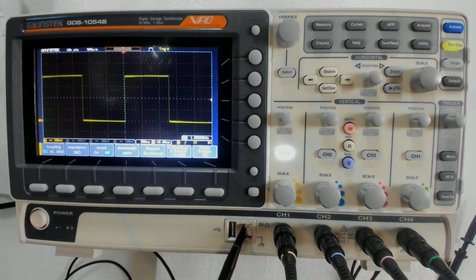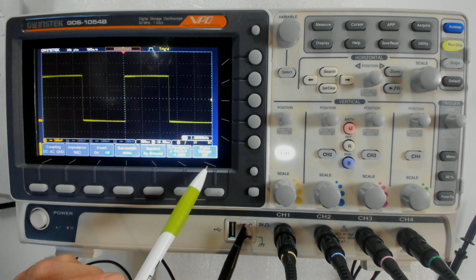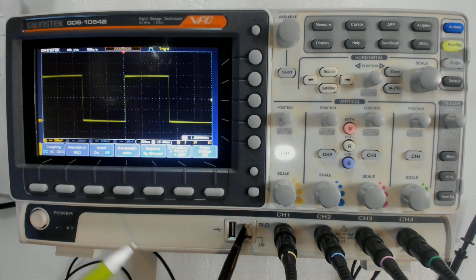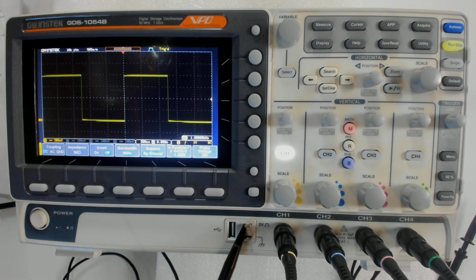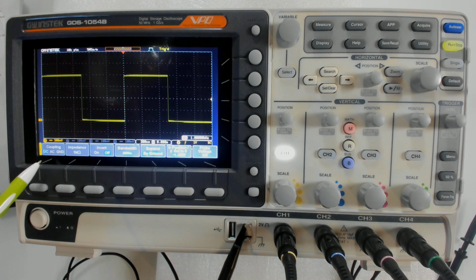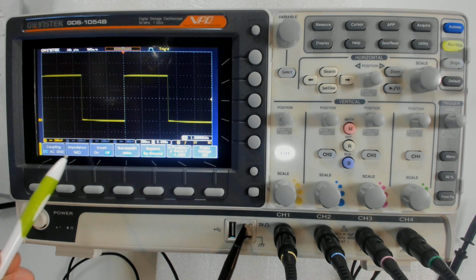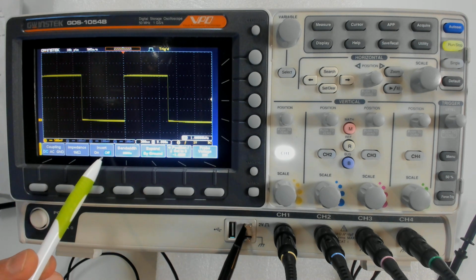Some of the highlights you can see are, I mean, you can see I took averaging off, right? I got sort of that thicker line now again. And looks good. DC coupling, bandwidth limit, 10 times, because I have the switch on my probe set for 10 times. And the heads-up display, which we see here from the channel menu by pushing this button, let's just look at all the little things it tries to help us see at a glance. It's telling us the coupling, DC coupling, but look, it also tells us the vertical scale, 500 millivolts per division. It tells us whether it's inverted or not. It's not, it's off.